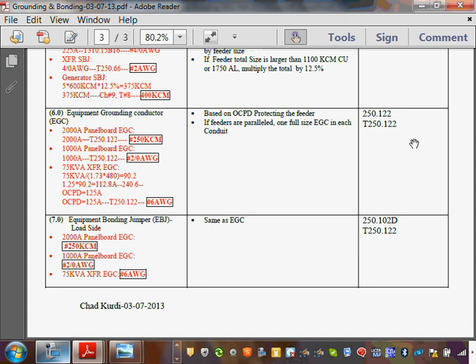Okay, so let's go to the 100 amp panel. I have multiple examples here. Here's my 1,000 amp panel. You take 1,000 amp to 250.122, which I trust that you guys have seen this table before, right? And it will get you a 2/0. Then my conductor has to be a 2/0. Typically, we do this, guys, if you're using PVC conduit. If you're using PVC conduit, you must. If you're using EMT conduit, then you have the option of using EMT as a grounding path, or rigid, or intermediate, or pulling an equipment grounding conductor. Also, you can pull an equipment grounding conductor inside. Any comments about the 2/0 with the 1,000 amp?